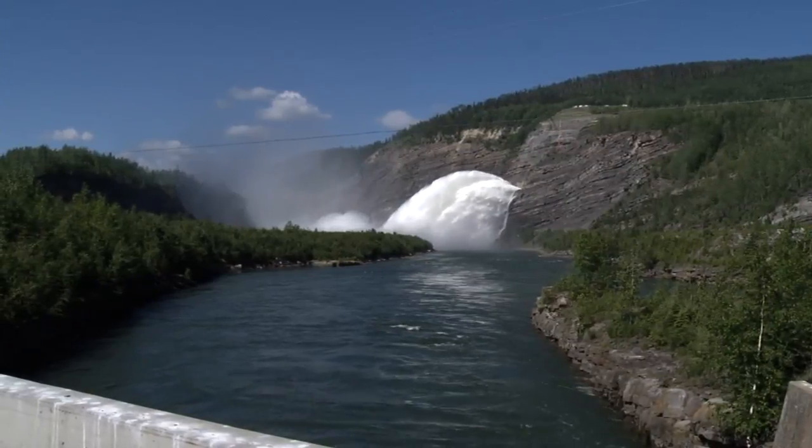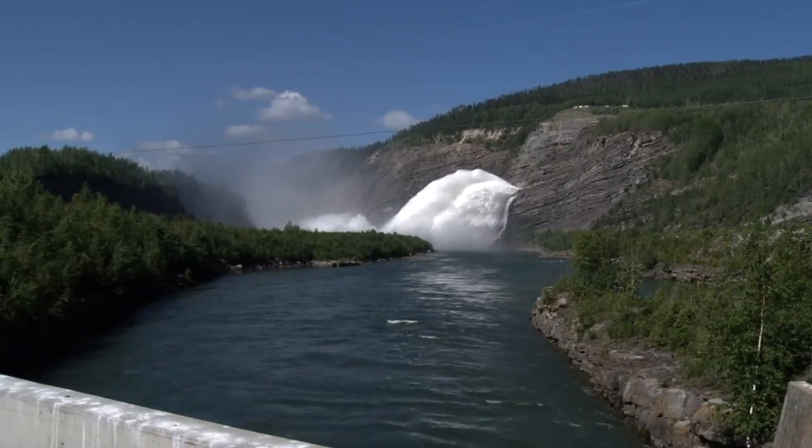The low point this year, as we come into the end of winter, was higher than it normally is, so we already started with a reservoir that's higher. Then add on a lot of snowpack and a lot of rain — all of that water flowing into the reservoir means we're full sooner than we might have otherwise expected. So we have to manage the water safely behind the dam, and that requires us to spill when the reservoir gets full.